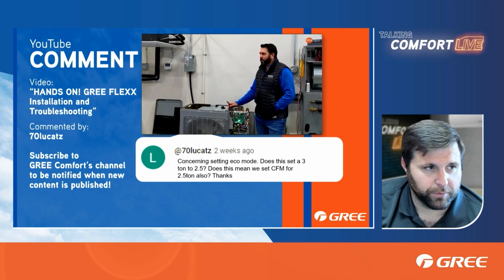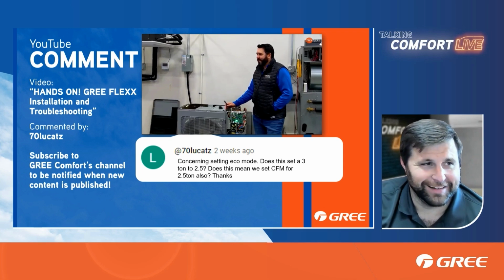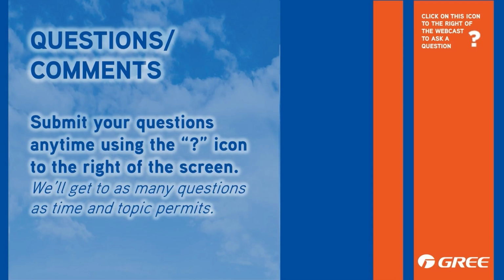Yes. And I think you could set it for 2.5 tons worth of airflow because it's going to be running economy mode on the outdoor unit. But I think even if you kept it at the 3 ton of operation as far as airflow, I still don't think you're talking about a minimal difference in operation. And it actually gives instructions in the service manual or installation manual about how to set those and use the eco mode and the strong mode to give that little difference of 1/2 ton.